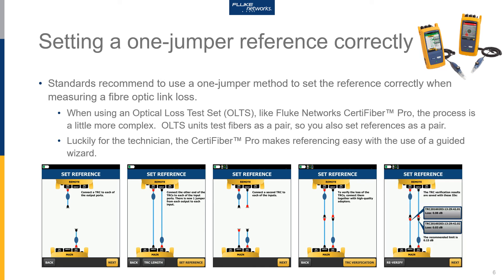Once the verification is complete, the instrument gives you a reading on the verification result, including the date, time, and the loss recorded. Our first cord set had a loss of 0.08 dB, and our second cord set had a loss of 0.03 dB. For multimode — which is what we have here — the limit is better than 0.15 dB, and these cords are good to go. For single mode when using an optical loss test set, it's 0.25 dB for the TRC validation check before you proceed to making measurements.